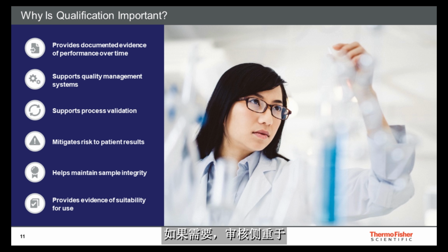The audit was focused on the organization that stores marketed products to be used as a reference standard if needed. Now, storage of these reference standards in the proper condition is critical and tightly monitored, as a loss of product reference could lead to a product recall, and nobody wants a recall, even if it's not a drug quality related recall. During the audit, we pulled all of the documentation needed to show that the unit was running within a qualified state. That included the initial IQ, OQ, and PQ documents.